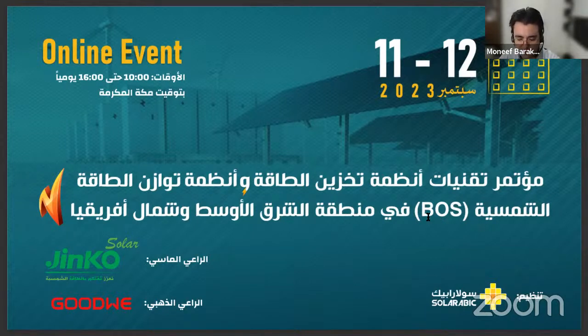You presented these different ways of testing the inverters, whether a solar inverter or an inverter used for energy storage systems, which got into a lot of technical details. Obviously, most of the sellers of these products claim that they conform to certain international standards, this IEC standard or the other one. Now, in your opinion, do you believe that we need more rigorous tests in excess of what is stated in these IEC standards in general?